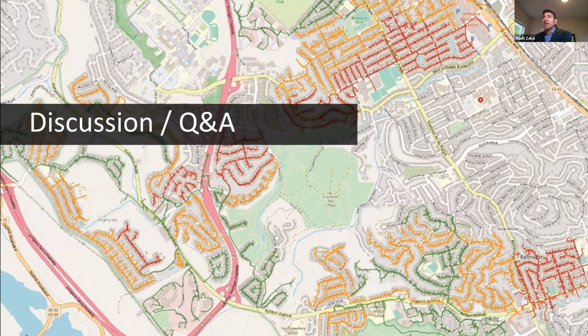Adarsh, I see Tyler asked a question that maybe you could answer: what do you mean by checking aggregate active power in the baseline model validation? I can give a simple answer. You have a feeder and you know the peak load is 3 megawatts based on your experience in the utility. As you allocate that load, say 3 megawatts, across 400 or 1000 houses, it's important to double check it. As we allocate load that's supposed to be consumed at peak across many distributed homes, commercial, or industrial customers, the aggregate of all that consumption happening at those houses, commercial and industrial sites should match what you expect at the feeder head. That's what aggregate active power means, or what we're referring to. Hope it's not too confusing.